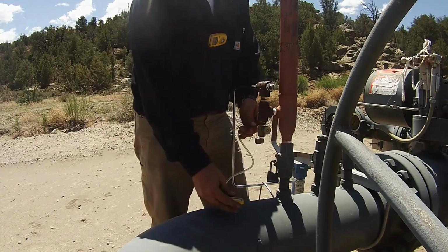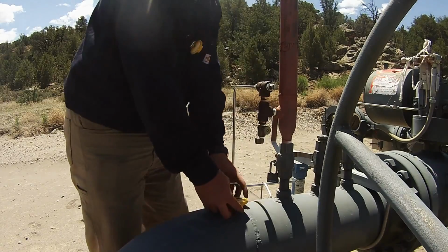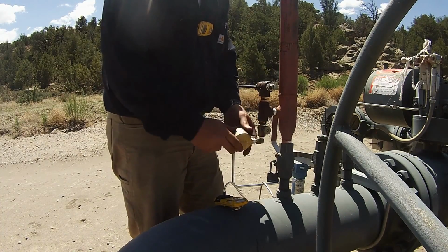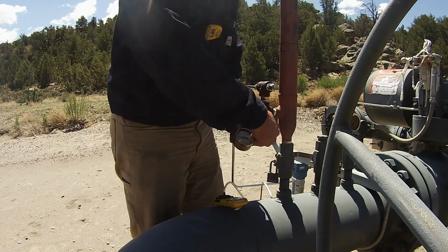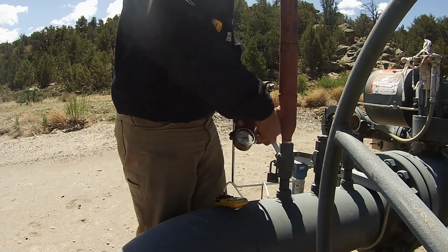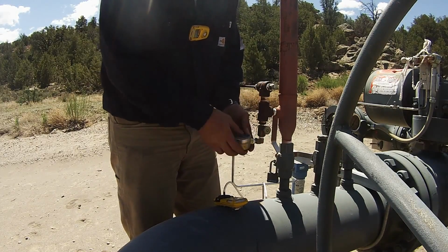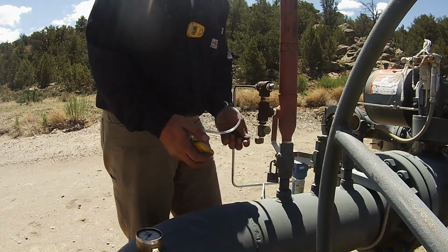We have an H2S monitor that we'll take H2S readings with. I forgot to turn that on, so we'll get that turned on. Next thing we're going to do is check our pressure. We always check our samples with PSIG, which is off of a gauge. Go ahead and open this up. And we have 165 PSIG. Close that off. Make sure your valve's closed before you pull your gauge off. And our H2S monitor is ready to go.